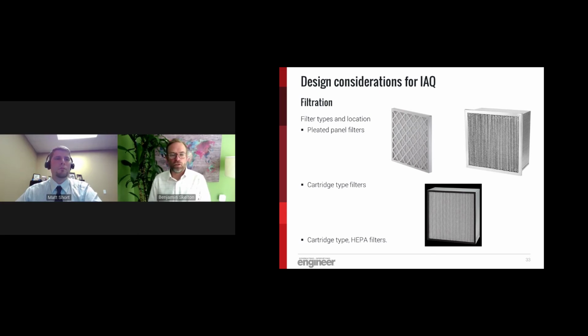The different filtration efficiencies that Matt just went through can apply to pretty much any type of HVAC system as long as you've looked at the design pressure drop. You can have these on your home furnace. You could have them in a rooftop unit. You can have a MERV 13 filter. In big office buildings, we have been recommending MERV 13 filters for a long time, especially buildings that are seeking a LEED certification or something along those lines, where that's one of the credit requirements. But in the recent past, we've been asked, can we get even higher filtration in our building?